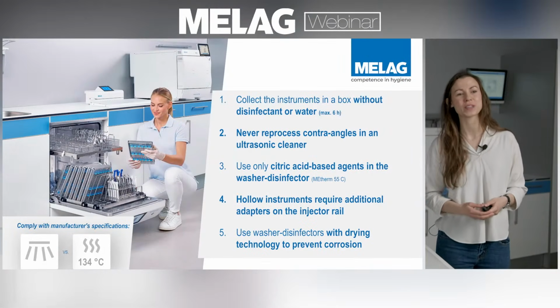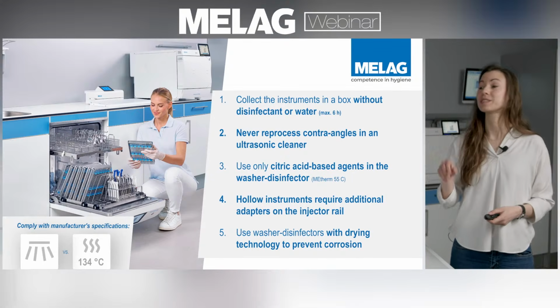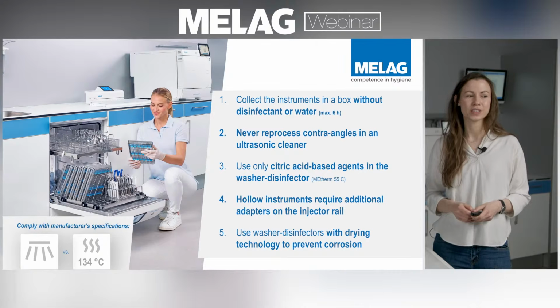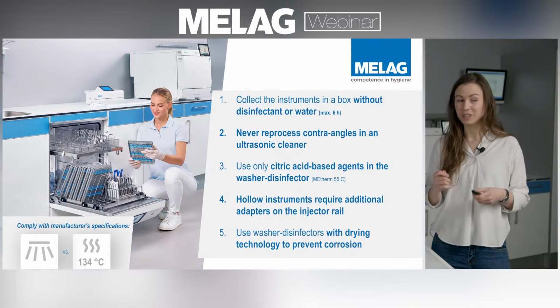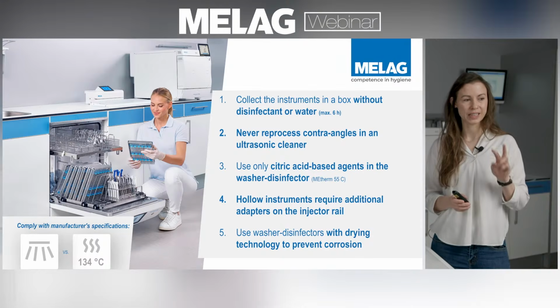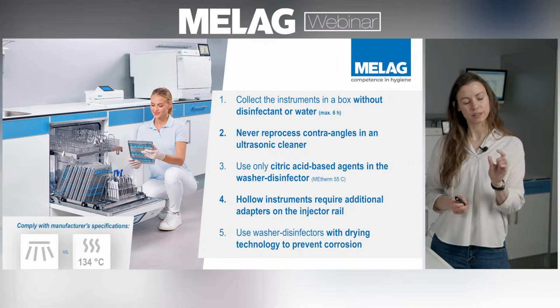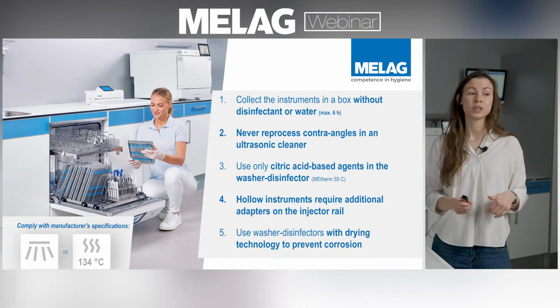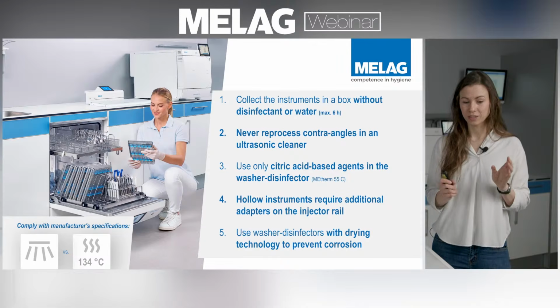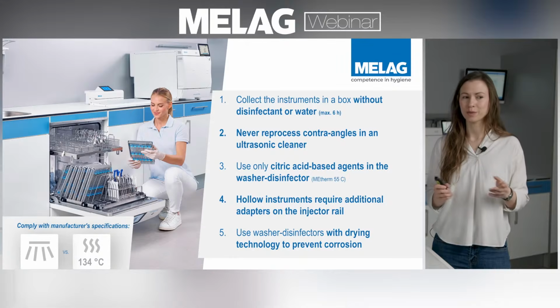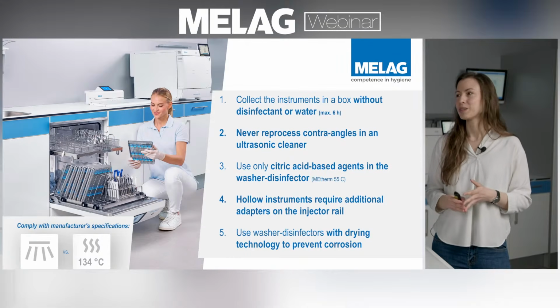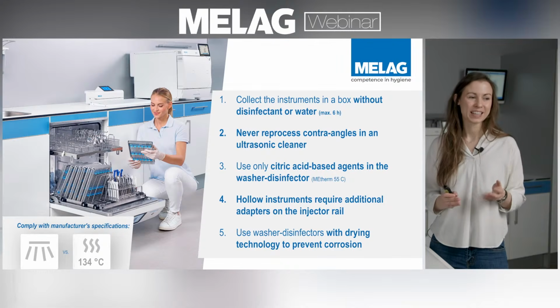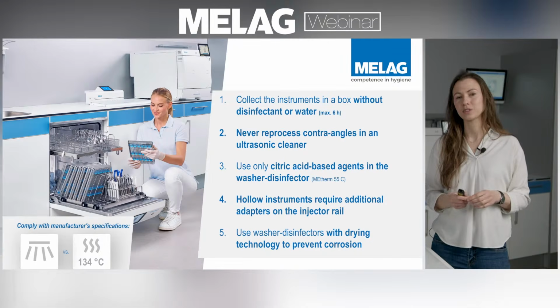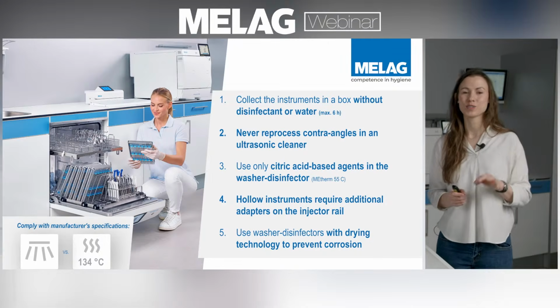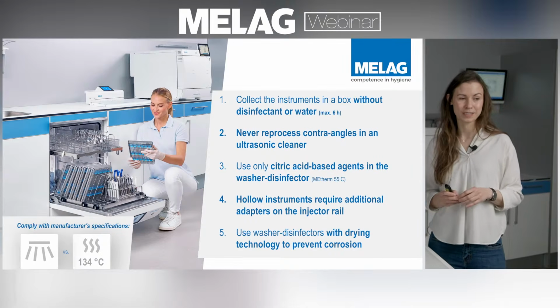Yes. First and foremost, I want to point out that this is not one of the 5 steps, but step 0: please check your instruments for different markings on them. Depending on whether they're allowed to be reprocessed or not, they have tiny symbols printed on them. You can see them currently in the bottom left corner of the screen. There's a little shower head. That means that the device is allowed to be reprocessed in a thermal disinfector. If it does not have it, do not put it into your machine, because otherwise your instrument might suffer negative effects afterwards. And then there are those 3 little squiggly lines with 134 degrees Celsius. This is the symbol that tells you that the instrument is allowed to be sterilized after it was disinfected.